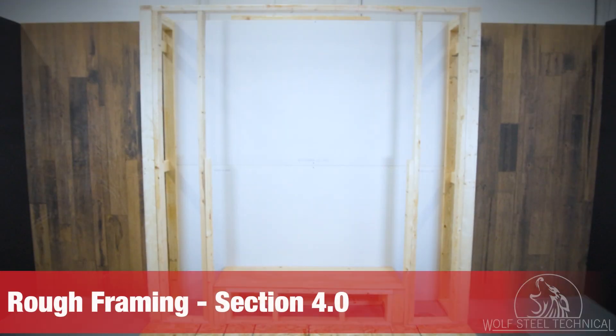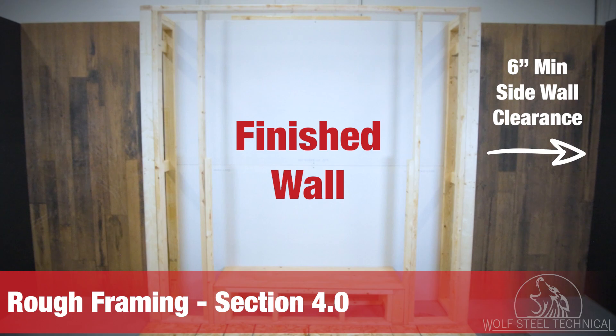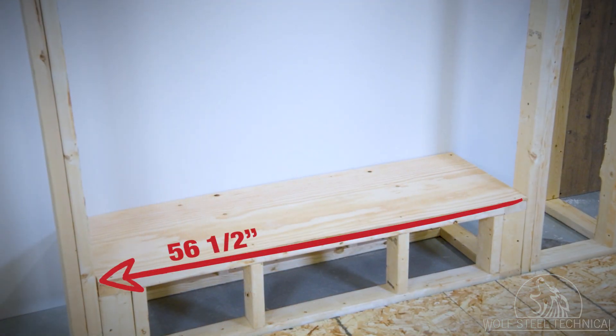In order to avoid the possibility of exposed insulation or vapor barrier coming in contact with the appliance body, it is recommended that the walls of the appliance enclosure be finished as you would finish any other outside wall of a home. Ensure interior and exterior enclosure clearances are always maintained. Minimum enclosure requirements are outlined within the manual and will vary depending on your installation.